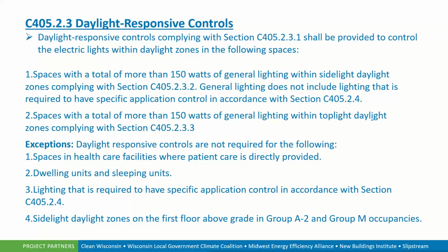Daylight responsive controls, making sure that we can reduce the amount of energy that's consumed when we have those daylight areas that are close by large groupings of glazing, making sure that we are able to reduce our lighting requirements or lighting draw, the amount of energy we use for illumination within the building, when we can take advantage of that natural daylight. And the daylight zone is defined as a portion of the building's interior floor area that is illuminated by natural light. And here are some of the exceptions when we talk about daylight responsive controls and where they may or may not be required. So again, we need to refer to that code section, or we'll follow up with the commercial lighting presentation, which goes deeper in depth to all of these chapters and how this is accomplished and laid out.